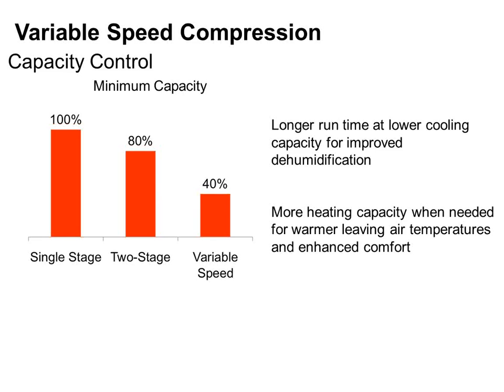If I go to variable speed compression, I can ramp down, in this example, to 40% of capacity. There's another variable speed heat pump I'm aware of that can ramp down to 25% capacity. So I get some pretty good turndowns with variable speed compression versus 1 or 2-stage compression. That's going to help me when I want to dehumidify. I can keep the evaporator coil wetter longer and dehumidify more if I run at a lower capacity.